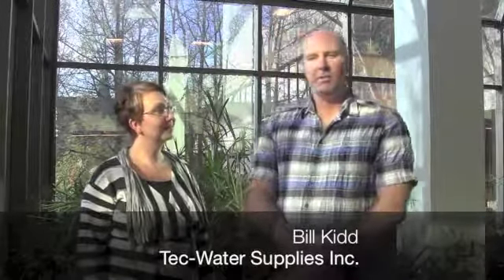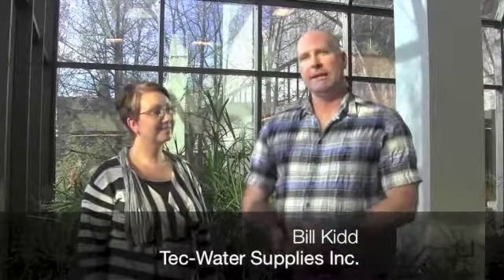You bet. But before we get to that, how does your guys' treatment system work? Well, essentially, when you're taking some surface water, there's lots of turbidity and color in the water. In nature, the actual particles all have a negative charge on them, so they want to stay in the water. That's why the water always stays either cloudy or dirty. So we introduce a coagulant into the water, because what that does is it makes all the particles in the water combine together. It's like a mineral magnet almost. And that's actually called a floc. So that's where the floc system got its name.